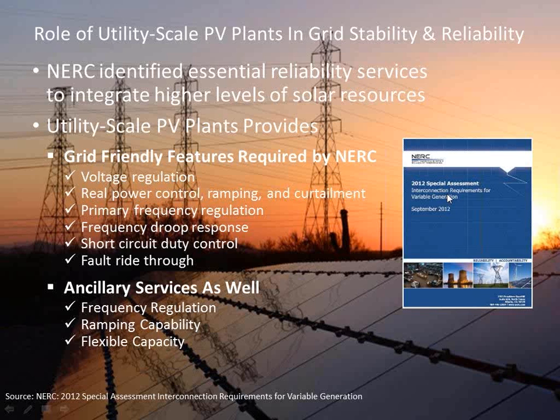Okay, so let me answer that. Unlike conventional generation, utility scale plants can actually respond really fast, much faster than any conventional generation. So generally the challenge is how to make the control system so the plant responds at a rate that the grid operators desire. If they want a 10% per minute kind of rate, we can slow down the response of the plant to achieve that.